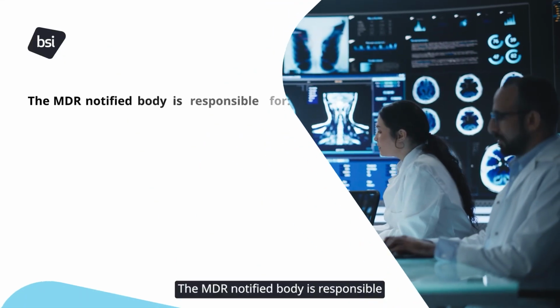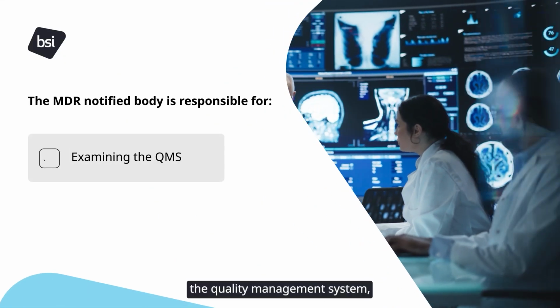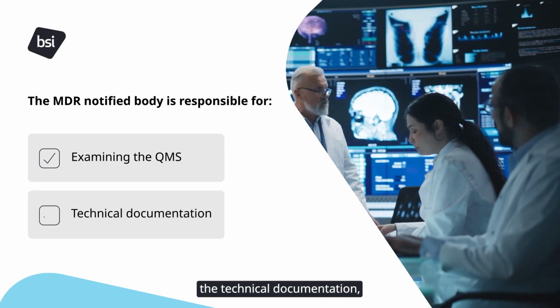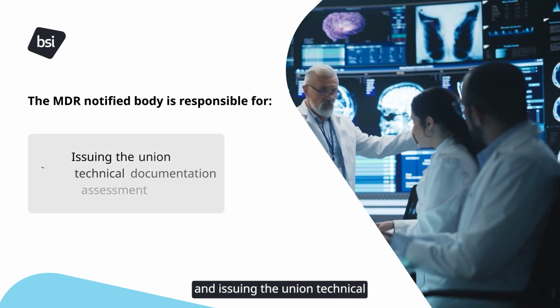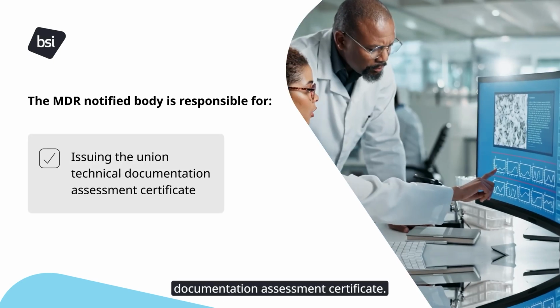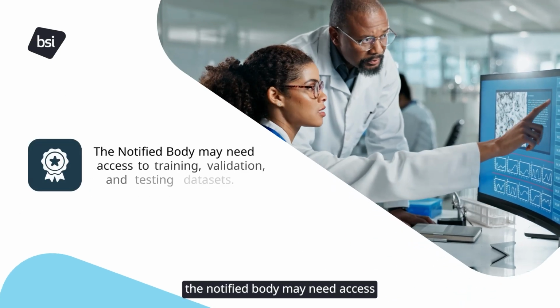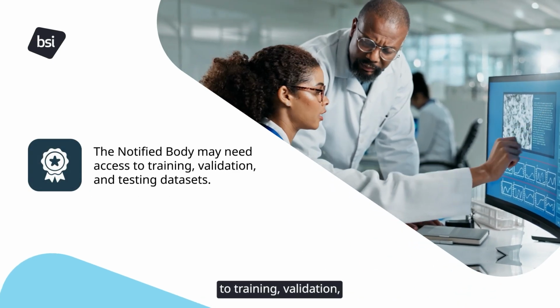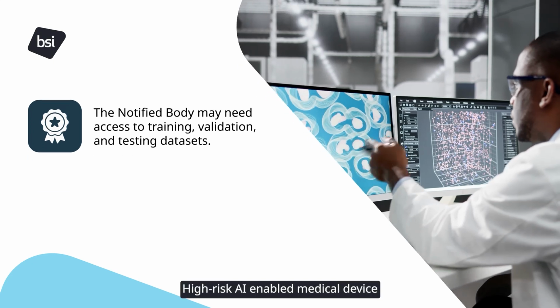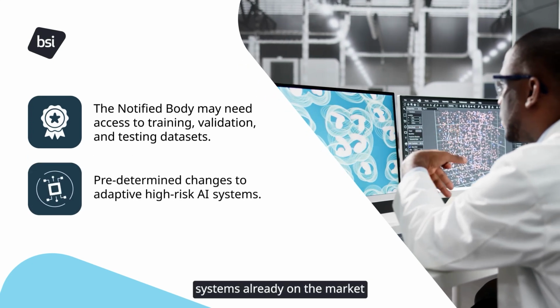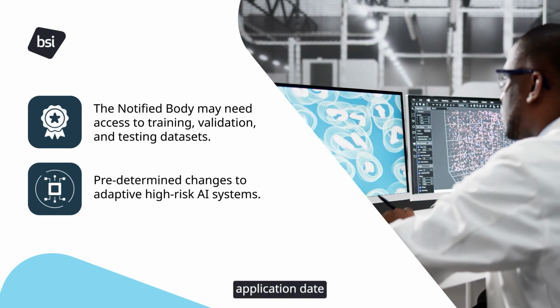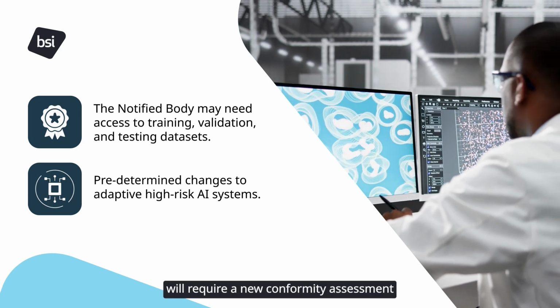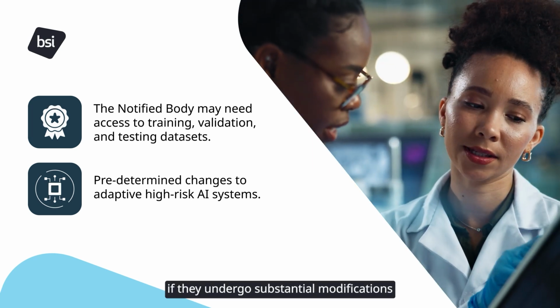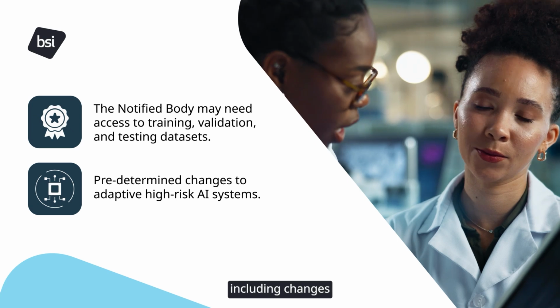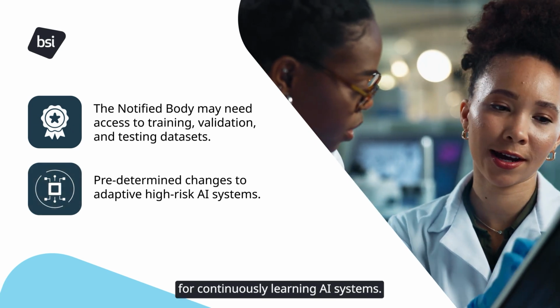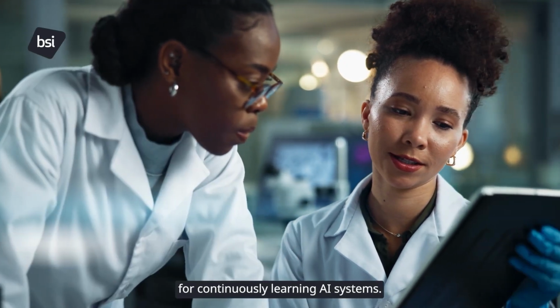The MDR notified body is responsible for examining the quality management system, the technical documentation, and issuing the Union Technical Documentation Assessment Certificate. To do this effectively, the notified body may need access to training, validation, and testing datasets. High-risk AI-enabled medical device systems already on the market before the AI Act's application date will require a new conformity assessment if they undergo substantial modifications after such date, including changes beyond the predefined range for continuously learning AI systems.